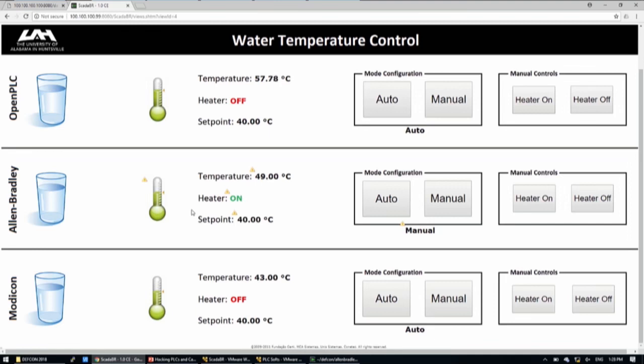So yeah, it is booting up, and you still see the exclamation points here? You'll see it till the end of the presentation. The problem is the application got corrupted, so the PLC cannot launch it again. The fault mode is always on. The only way to make it work again is to reprogram it with the ladder logic. This is creepy, right? If you lost the ladder logic, you're screwed.